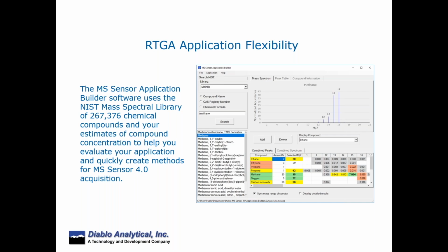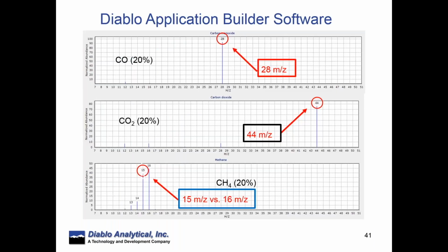And you can see 16 is the highest, but it avoids choosing 16 because there would be an interference with oxygen. So the software recommends 15, which is essentially the next highest ion for methane that does not interfere with another component. So this makes it much easier and quicker to take a new application and put a new method together, and then we're able to quickly make a method out of it, which I'll show you in a minute. So in this case, 28 for CO, 44 for CO2.